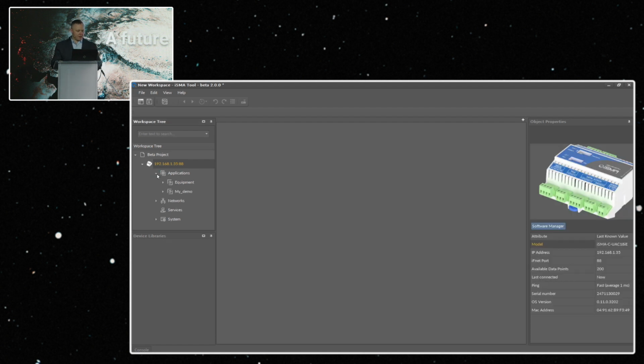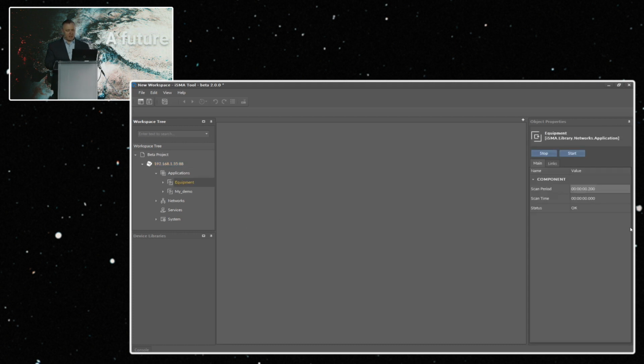The application container is where you put the application. You can have many applications in that container, each set up with different scan periods. Our applications are cycle-driven, executing every certain period of time according to the scan period, and each application can have a different scan period—they don't all have to run on the same one. The scan time is the actual physical time required to run the application. The equipment application is empty, I believe, but My Demo has a few components, and its scan time is about 4 milliseconds—very fast.